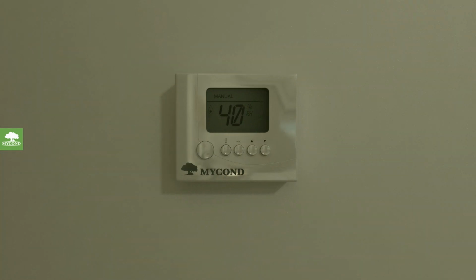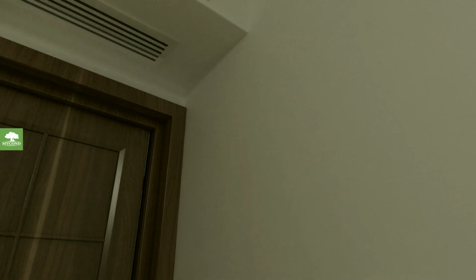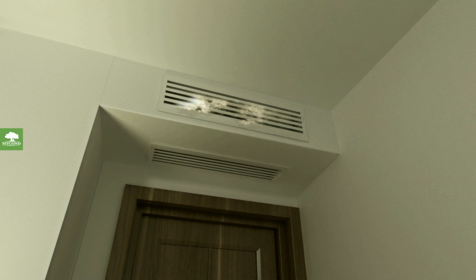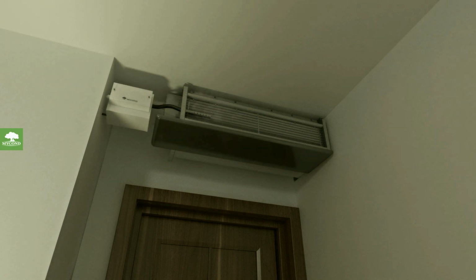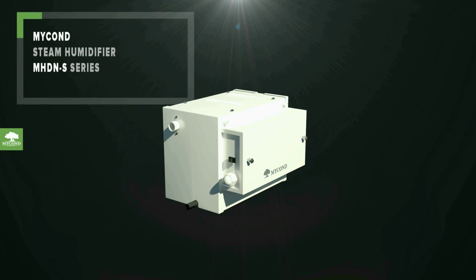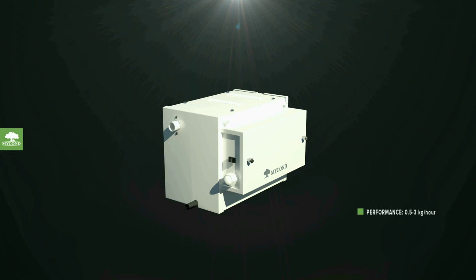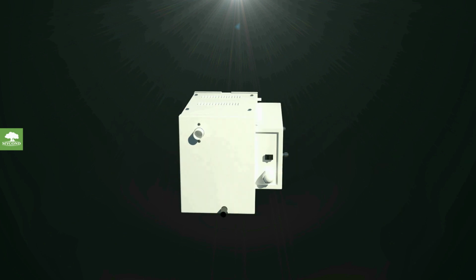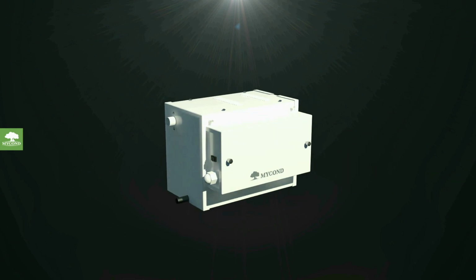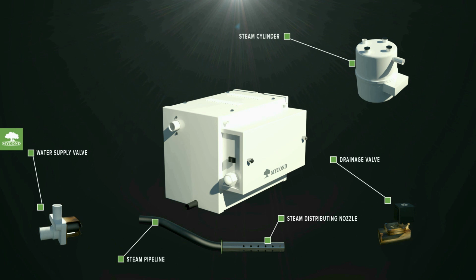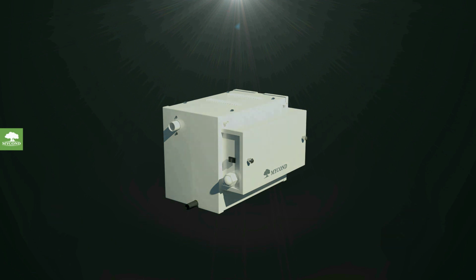Mycond steam humidifiers of MHDN S series are designed to work with duct fan coils or internal units of duct-type air conditioners. Humidifiers performance from 0.5 to 3 kg of steam per hour. You can install this humidifier in each room within the duct unit of an air conditioning or heating system. This will allow maintaining the individual humidity in the premises and saving on operation.